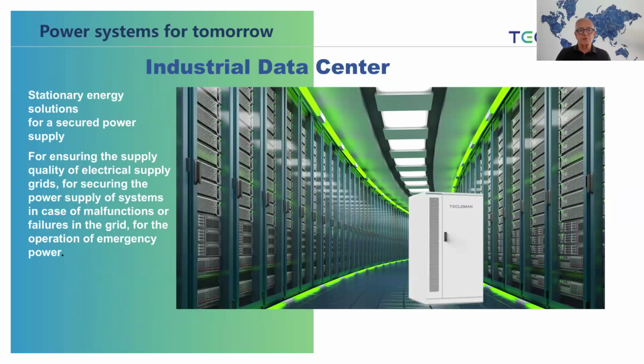They need this storage system because in the past they only had lead acid batteries, used only for emergency effects. If a data center has around 10 or 15 emergency events a year, they can live with lead acid batteries, because the lifetime cycle of lead acid batteries is 1,500 cycles - enough if they have a problem 15 times a year.